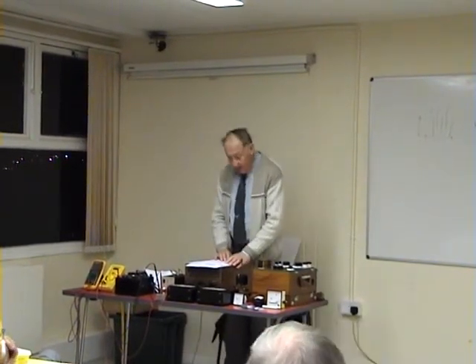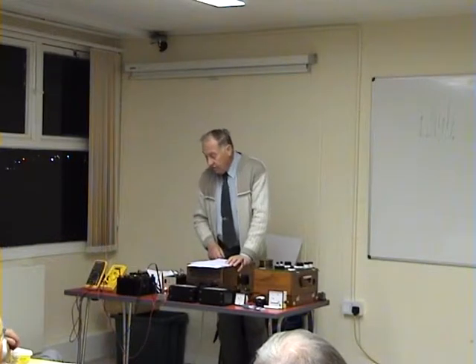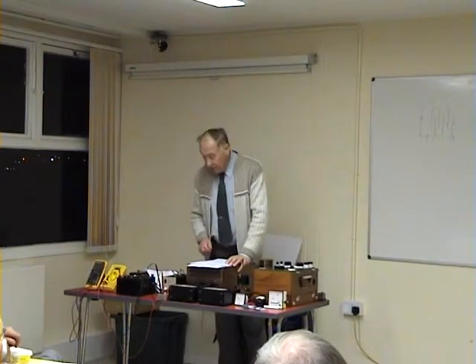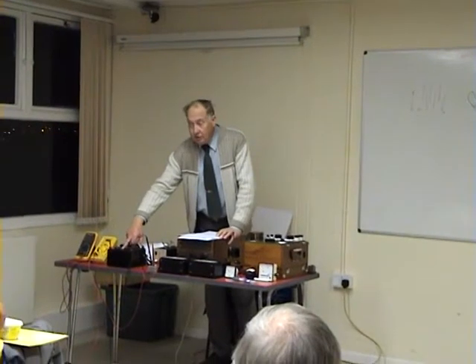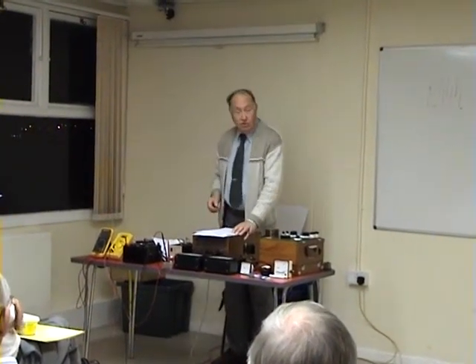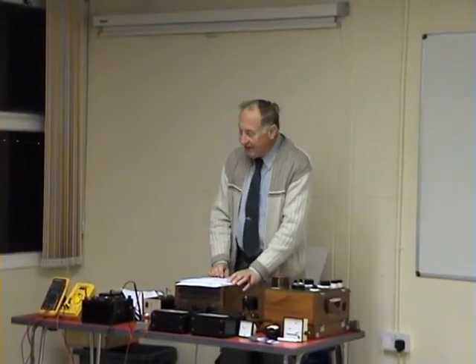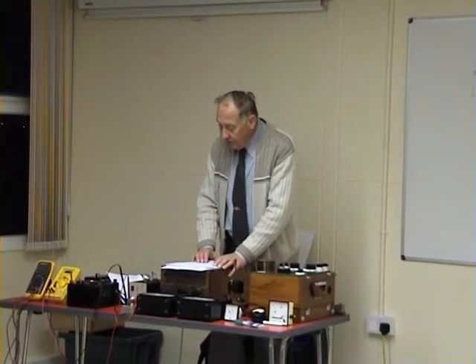AVOs don't have fuses, but they do have a cutout. This button there is linked to the whole meter movement, and if that pointer bangs over a bit fast, it hits a trigger, and this thing springs out and breaks the circuit completely. Now, in all my time, sorry, I'm sounding like an old boy here. In all my time servicing, repairing and calibrating instruments over the last 40 years, I've never encountered an AVO meter which had actually been damaged by overload. That's a flat statement. That velocity trip really works.